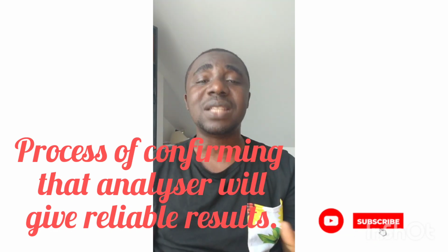So what you do is, following the installation of that analyzer, you need to do maintenance and calibration. Once it has passed maintenance and calibration, the next thing to do is the quality control sample. When you run the quality control sample and it passes, you then need to test that analyzer with patient samples, all kinds, normal and abnormal.